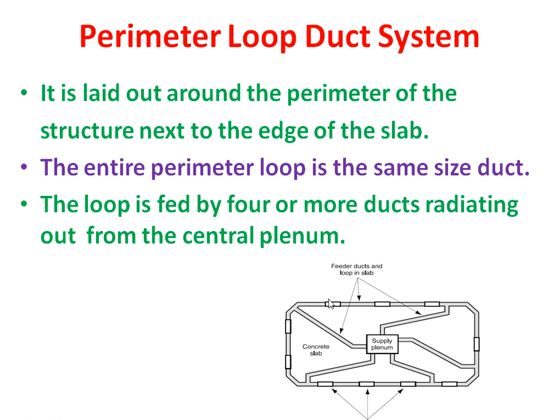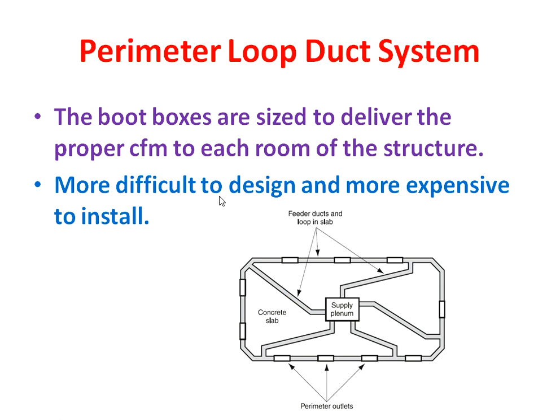The perimeter duct is always constructed at the edge of the slab. The perimeter loop has the same duct size throughout its entire length — there is no change in size. The loop is fed by four or more ducts radiating from the central plenum, with four to five ducts supplying air from the supply plenum to the perimeter duct.